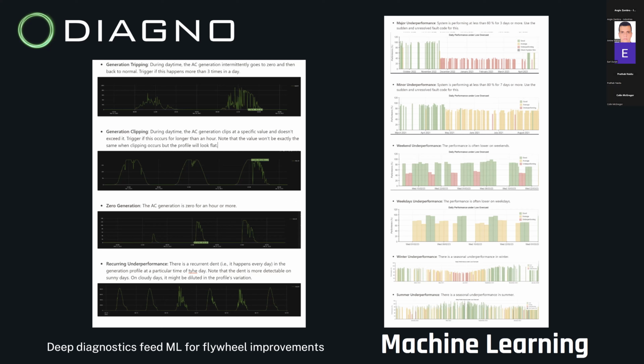At this stage, we've defined level 1 and level 2 faults. You can think of level 1 as a suite of AC faults, and level 2 as everything beneath that—DC, inverter fault codes, things like that. The machine learning can go from level 1 to level 2 and provide a deep diagnostic based on all the issues it's seen thus far and how we've trained it.